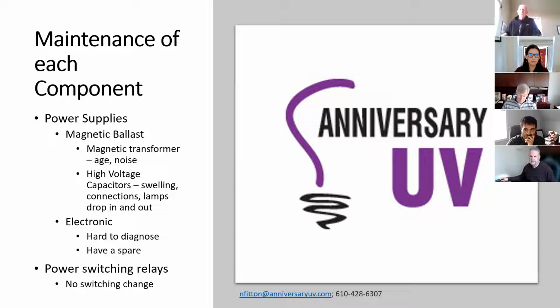Your power switching relays can be electronic or mercury. They tend to last a long time. The only warning you're going to get when they stick is that when you switch from low to medium to high, or low to high, you won't see the intensity of the lamp change. When you don't see that intensity change, you've probably got a bad relay. These relays are very inexpensive and very easy to change out.